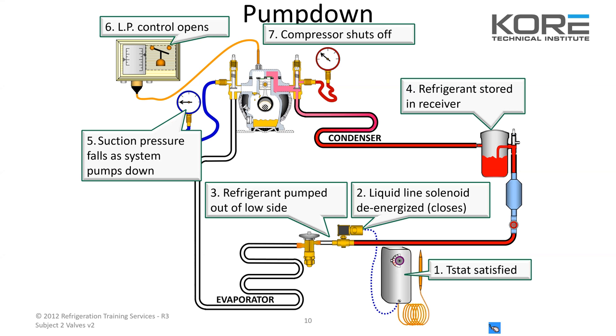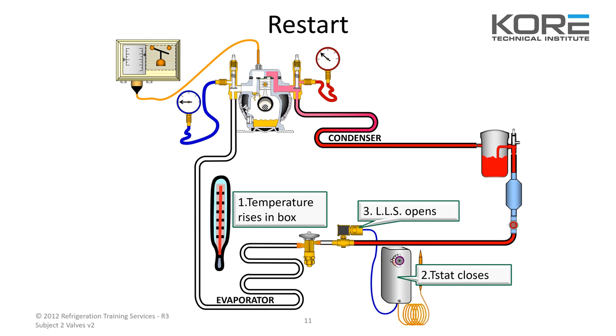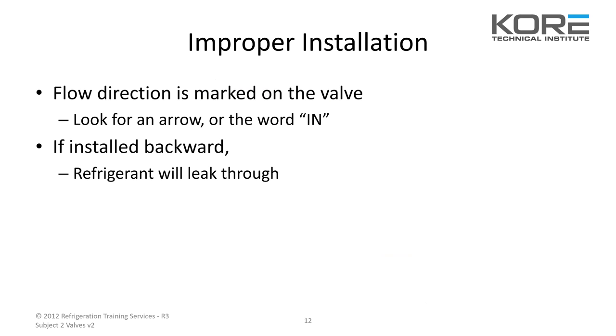Any questions on this cycle? On restart: temperature rises in the box, that tells the thermostat it needs to close. Once that closes, it gives power to your solenoid valve, opens back up, lets the flow of refrigerant go through the coil and up to the compressor. The low pressure control: pressure rises, closes the switch, compressor will restart, refrigerant goes back into the system. It's pretty simple.